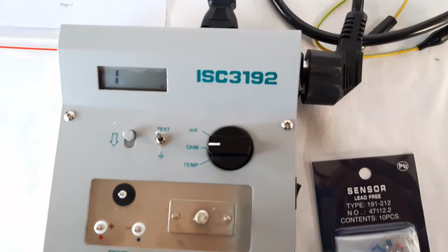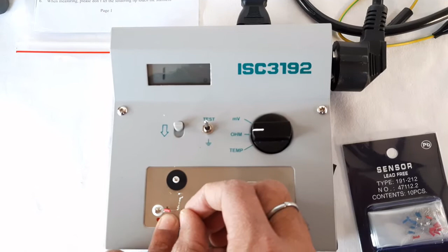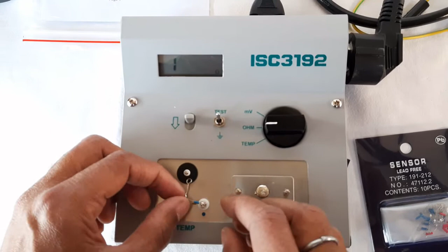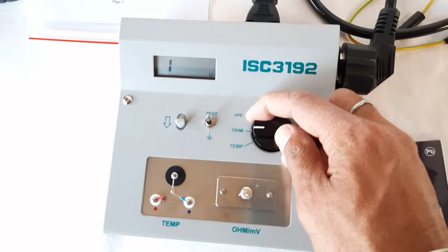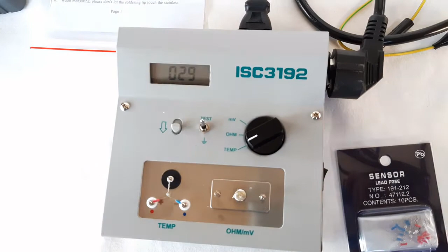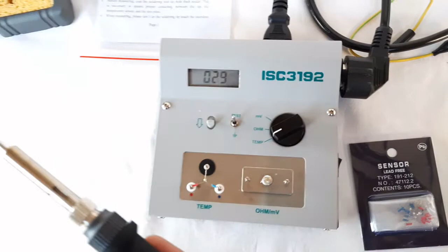So first of all, we will measure the tip temperature. We need to just put this thermocouple sensor on this port. Positive polarity should be matched to this red symbol, and negative should be matched to this blue wire. So this is how it is connected. Red one to the red terminal, and blue one to the blue terminal. Then we will just push this lever downwards and insert the thermocouple this way, and release this, so that appropriate tension is provided to this thermocouple, and just turn the knob to the temperature setting. Now it is showing the ambient temperature.